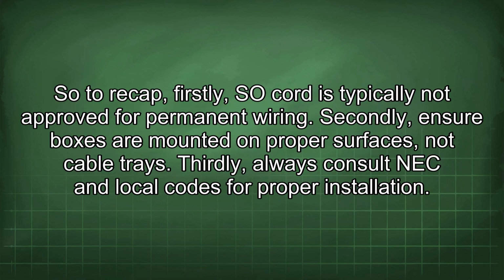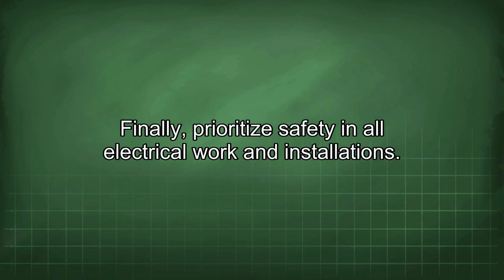So to recap, firstly, SO cord is typically not approved for permanent wiring. Secondly, ensure boxes are mounted on proper surfaces, not cable trays. Thirdly, always consult NEC and local codes for proper installation. Finally, prioritize safety in all electrical work and installations.